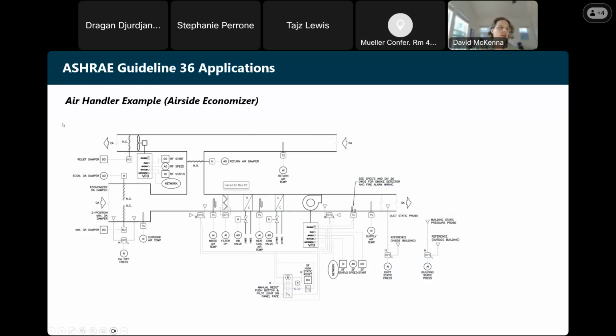So as I mentioned earlier, an increasingly large part of what we do as mechanical design engineers is providing the control strategies and controls schematic diagrams to communicate to the controls contractor and ultimately tell them how we envision this building to run. So each of these circles here, that hopefully y'all can see, indicates a controls point for this piece of equipment. This is one air handler with, I don't know how many, a lot of points. I didn't count them, but you can quickly see how this building could have thousands of points if you have multiple air handlers all serving that space. So each one of these is associated with either an analog output or an analog input or a digital input, digital output to the BMS, or building management system.